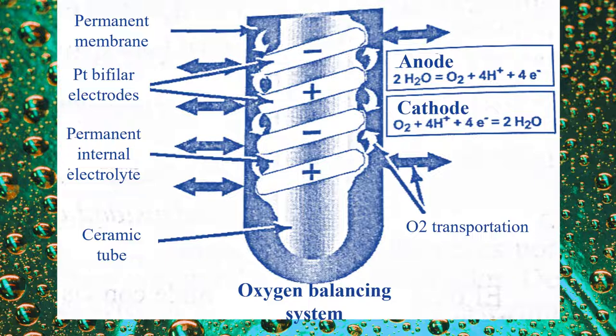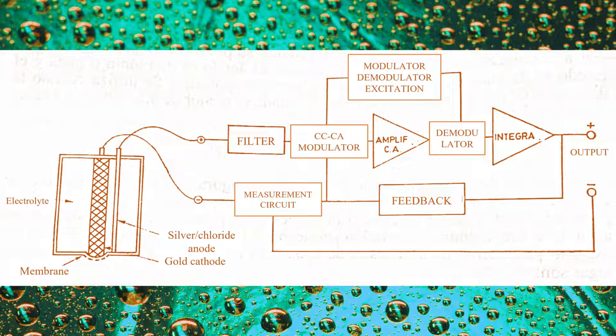The reactions are the ones you can see on the screen. Diffusion continues until the partial pressure of oxygen is equalized on both sides of the membrane. The current required to maintain this equilibrium indicates the concentration of oxygen in the solution.